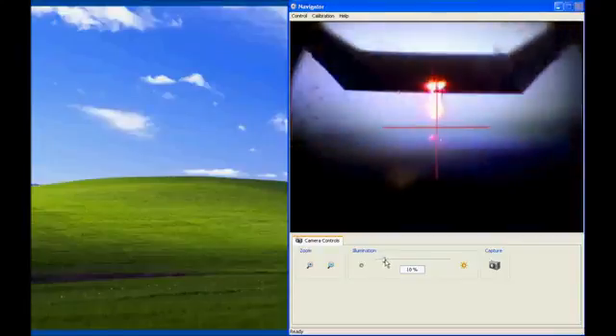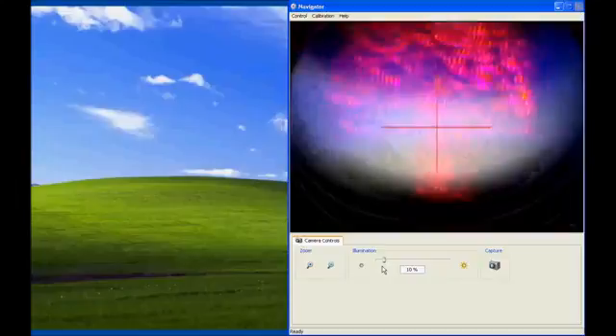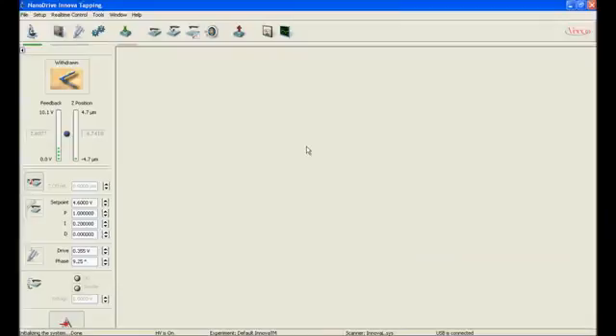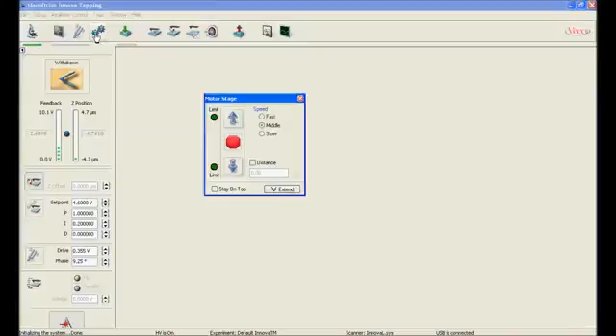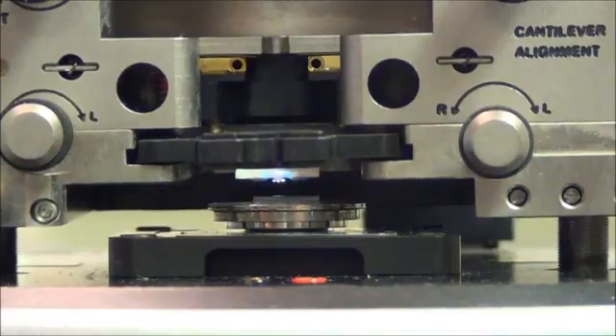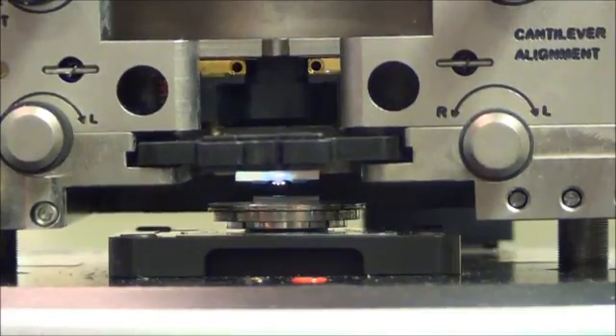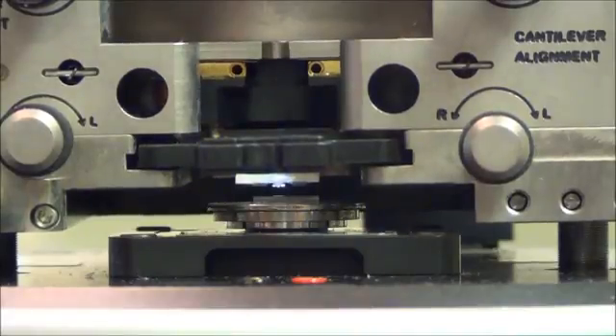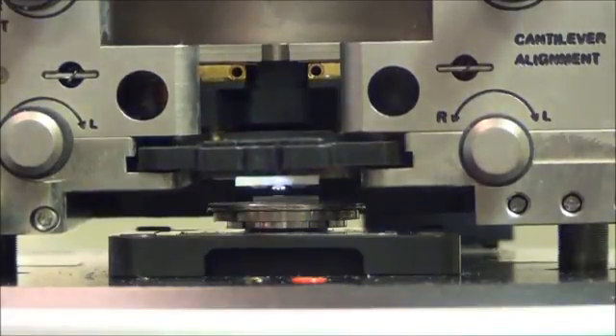Our focus should be between the cantilever and its mirror image. This calibration grating has some specs on it, so we focus on those. Click the fourth icon, the one that looks like gears, to open our motor stage controls. These up and down buttons lift and lower our tip to the surface. Never use these controls if the tip is in contact with your sample. As we approach the surface, keep an eye on the stage itself. The goal is to get close without actually touching.